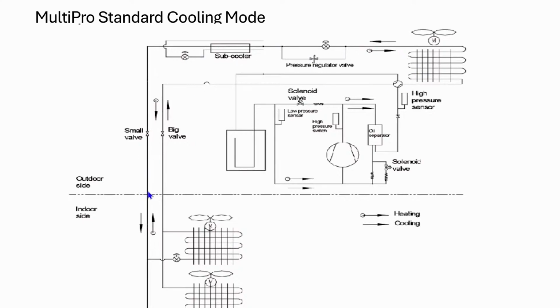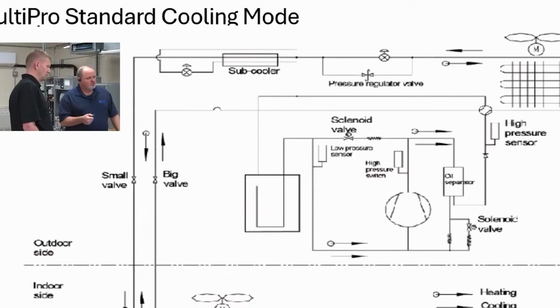If I've got a restriction, let's say I've got one indoor coil and one outdoor coil, when that unit fires up, that head pressure, if you watch your gauge, will go way up. And then all of a sudden it starts falling back down. The reason is that you've pushed that liquid up against that block, and it can't go, it can't go. So now it just starts stacking that liquid all the way back into our condenser coil, and the refrigerant's just sitting there stagnant with nowhere to go. And since I'm not able to suck any back to actually pump it, I can't build that pressure anymore.